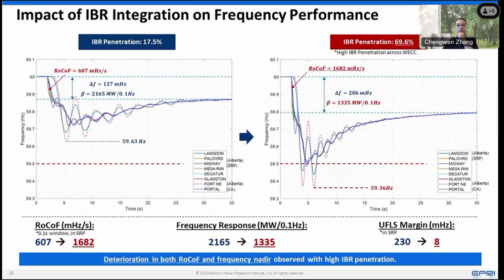It's almost touching the UFLS threshold, but in the base case, it has about 230 millihertz from the UFLS. So we can expect to see a significant change in frequency dynamics in the system if you have a large number of IBRs replacing synchronous generators, assuming they are not providing frequency support.